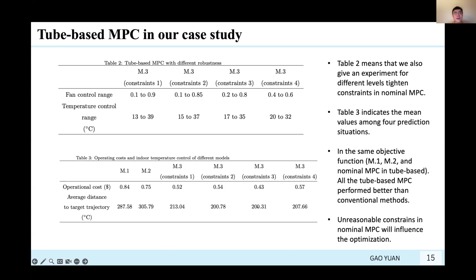Here is about the operational cost and the average distance to the target trajectory, because we have a very strict indoor air temperature set point in this case study. So it's about 50 percentage points for the operational cost saving, and relatively good performance in the target trajectory.